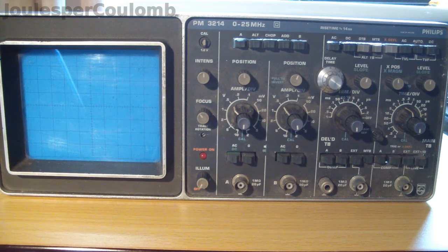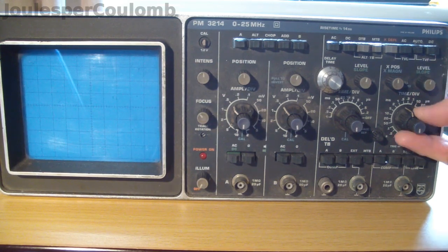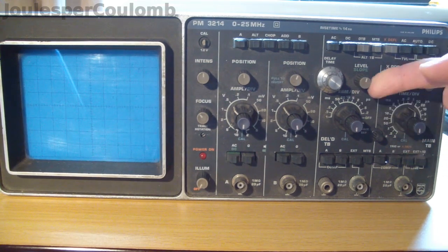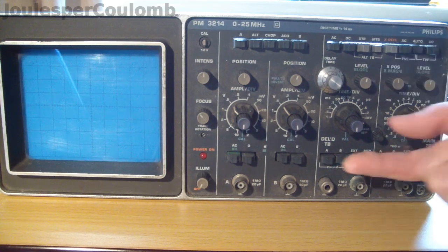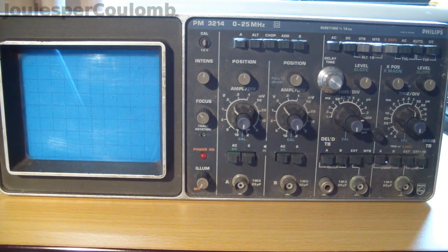It can also be used as a secondary trigger and time base. So for example, one could set it up so that trace A is displayed according to this trigger level setting and this time base, but channel B is displayed according to this separate trigger level and this separate time base, and so that would make it easy to display signals of very different frequencies, or two signals that are not related to one another in frequency.